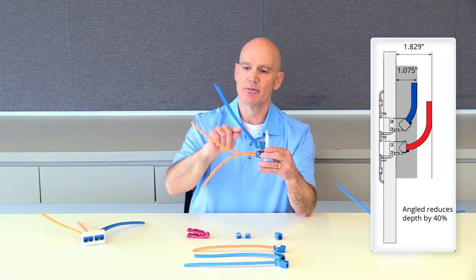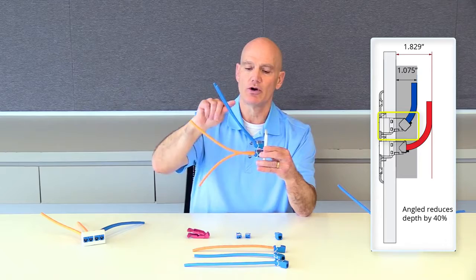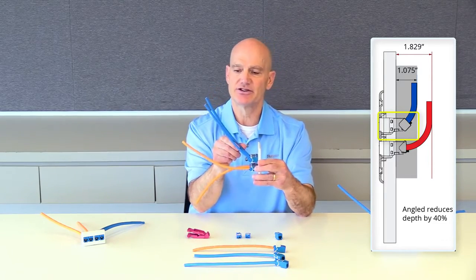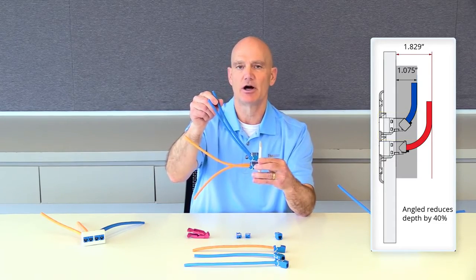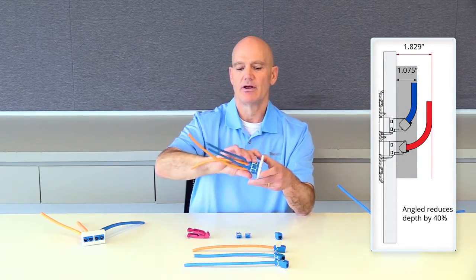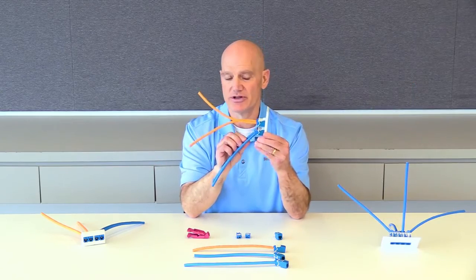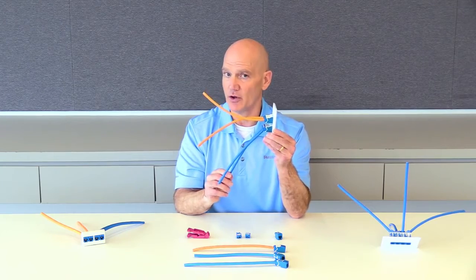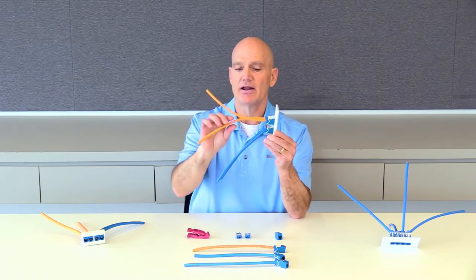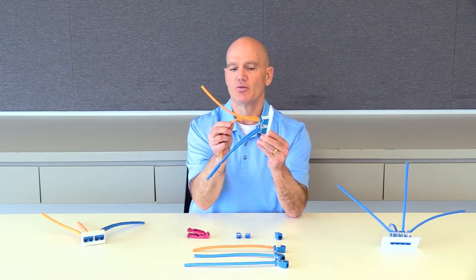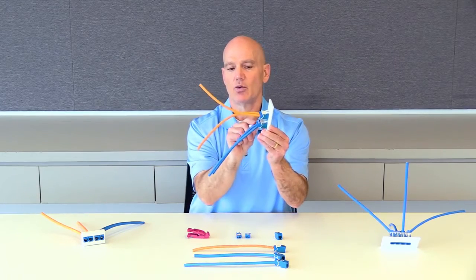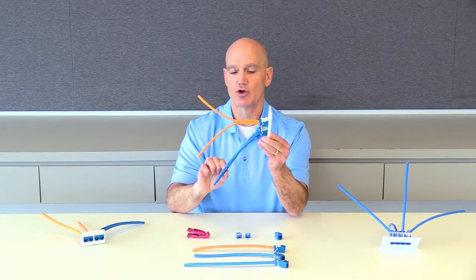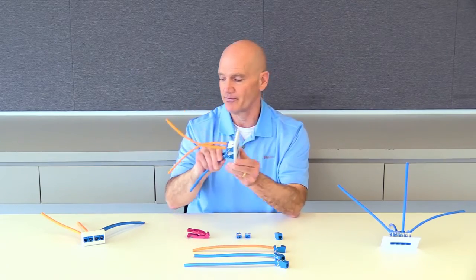But let's say the cable's coming from the ceiling, the upward orientation of the 45-degree angled wire cap allows us to start the direction of that cable in the upward position. If we were to use the downward position of that same wire cap and the cable was coming from the floor or beneath the floor, again, with the straightaway orientation we would exceed the bend radius, whereas the downward orientation already gets us having the cable going in the down position.